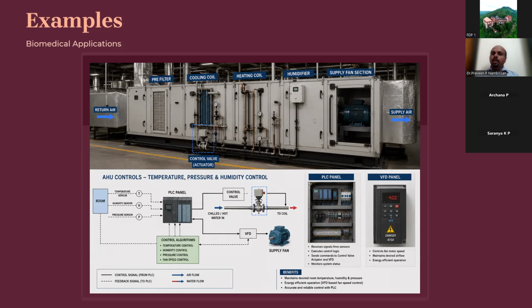So now I wanted to share how the blower motor works. I told you that supply air can be increased or return air can be decreased. How will we do all these things? By using the blower motor speed. Blower motor speed means it runs at a particular speed. How will I control the speed? By using VFDs. Now we are coming into the picture: variable frequency drives.